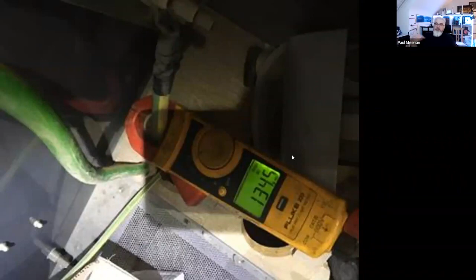So moving on. There's the reason. These are two images from two separate installations, kindly donated by a peer who we love and respect. One was an installation doing a brand new commercial fit out - it wasn't energized yet, they'd connected all the bonding in, and what they found was current going through the pipes to the point where it got the pipe so hot the lagging at the weakest point, where the joins over the clips, had melted and fallen off. The other installation had current so high through the gas network it had melted the meter, which is mind-blowing. It's crazy.